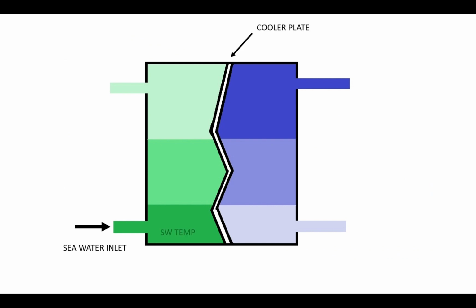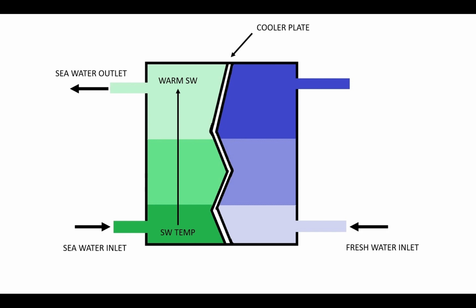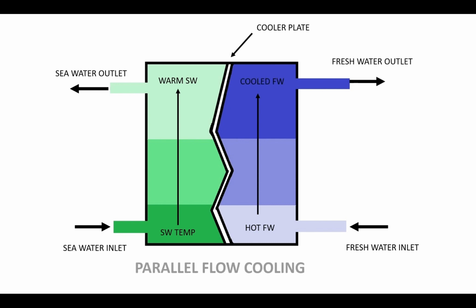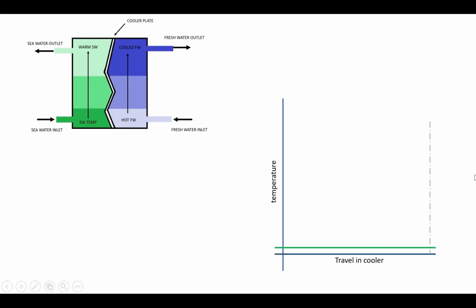Parallel flow cooling. The inlets of seawater and fresh water are both located at the bottom of the cooler and flow at the same upward flow, leaving at the top of the cooler. Let's look at the performance diagram of parallel flow cooling. The seawater inlet and fresh water inlet will enter the cooler at the same time.